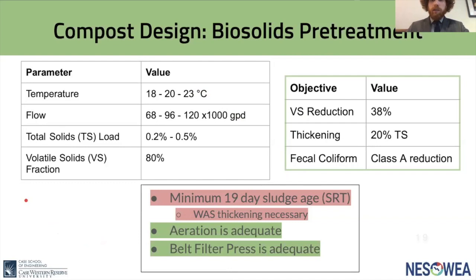To ensure the compost facility will be successful, we evaluated the biosolids pre-treatment process — particularly the aerobic digesters — to confirm that solids produced are appropriate for composting and safe for handling. On the left is a table of digester operation parameters including seasonal temperature ranges, a peak flow of 120,000 gallons per day, and a range of total solids loading. We assumed a volatile solids fraction of 80%, typical for waste-activated sludge. Our objectives for the final biosolids product are: reducing volatile solids by at least 38% for odor control, thickening to 20% total solids, and meeting class A biosolids standards for fecal coliform.